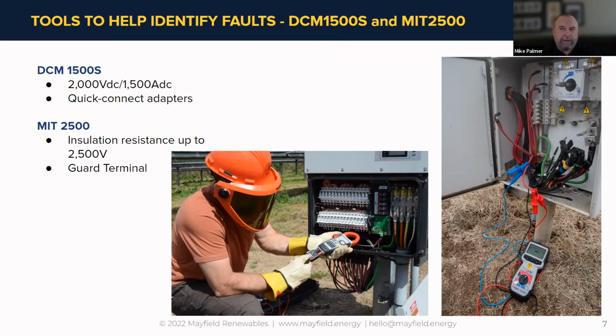But I think our PV technicians have figured out a way to sectionalize at the string level and then go module to module or section to section to figure out where their trouble is. But everybody has to admit it's the longest endeavor we do in troubleshooting. And ground faults, that's our future. We're going to really work at Megger on making it easier with content delivery and tools that'll allow you to find ground faults faster, until those inverter diagnostics catch up. So anyway, right, I'm good with this one.